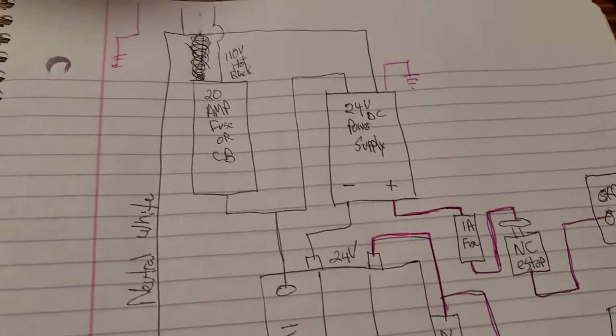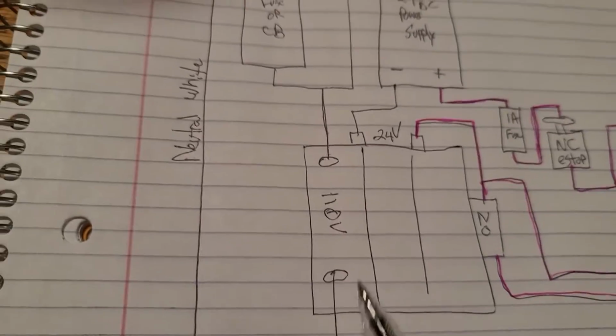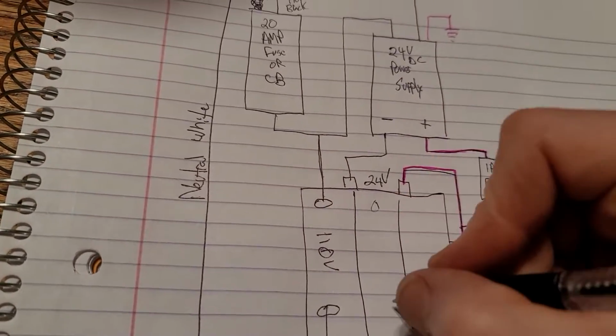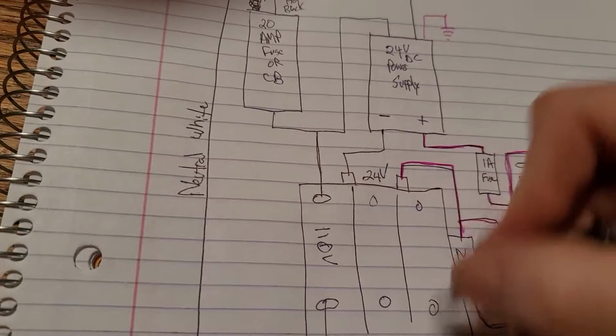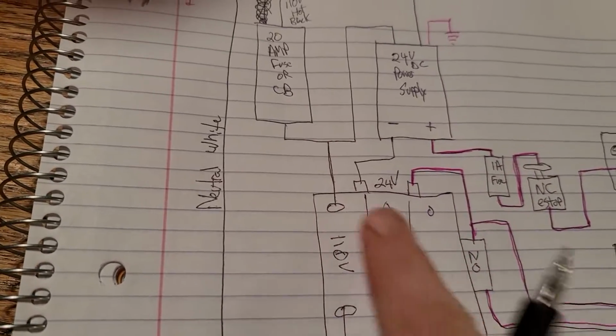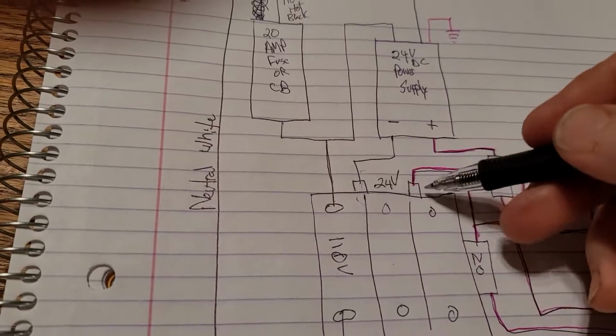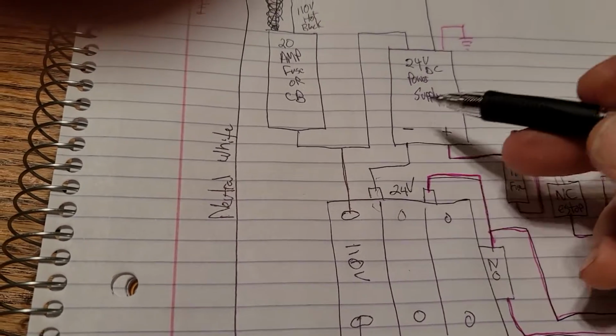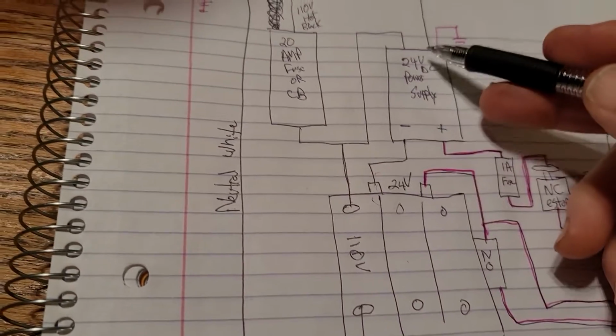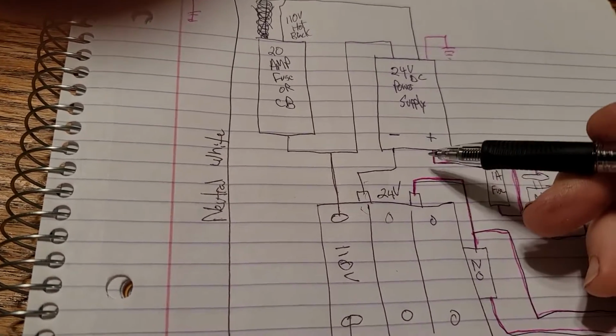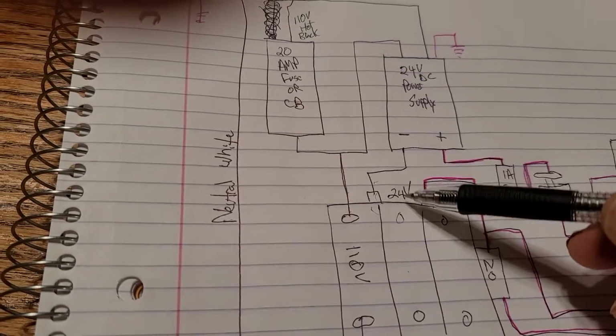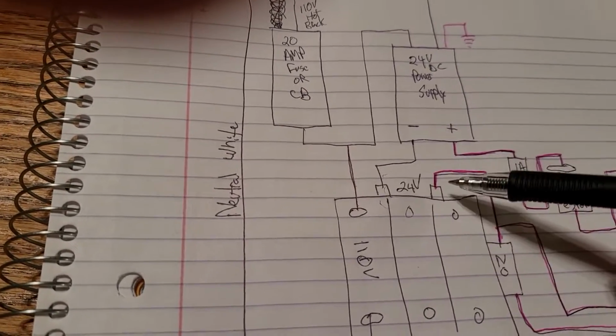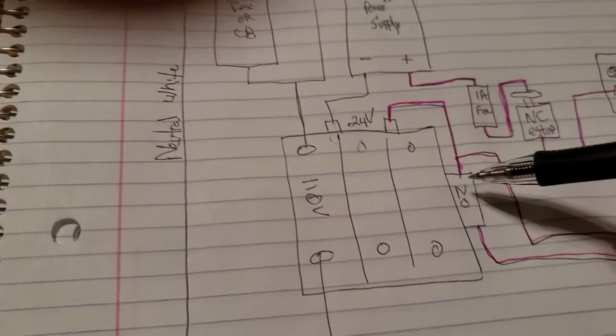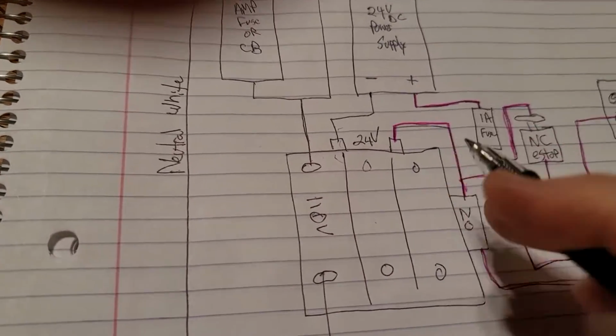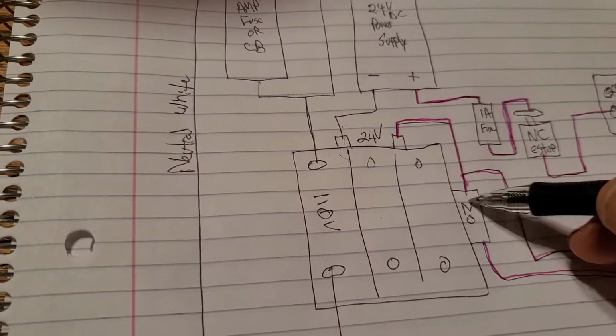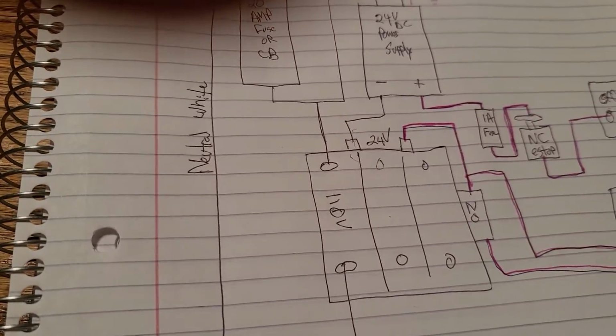Now, on a contactor, you usually have 3 main screws right there, 1, 2, 3, and those get connected when the coil, that's what these 2 little buttons here at the top are, when the coil is connected to its control voltage. In our case, we're going to use a 24 volt DC control voltage. So you want to make sure that the contactor's coil is rated for 24 volts DC. Now, you'll also notice I've got a little box out here. Almost every contactor has at least 1 and sometimes 2 normally open contacts on it. And that's important when we get to the control.